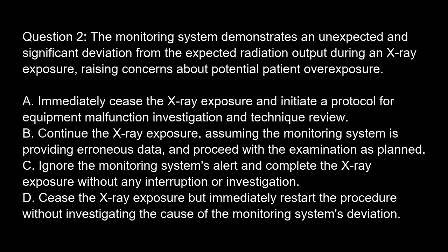Question 2. The monitoring system demonstrates an unexpected and significant deviation from the expected radiation output during an X-ray exposure, raising concerns about potential patient overexposure. Option A. Immediately cease the X-ray exposure and initiate a protocol for equipment malfunction investigation and technique review.